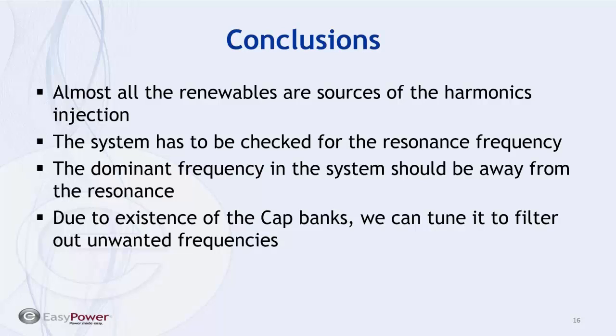The other thing is that when you do the frequency scan with the cap bank alone, and then you add an inductor and do the frequency scan again, you would notice that the pole has shifted. And if the pole has shifted, then you may sometimes need to revise some numbers.